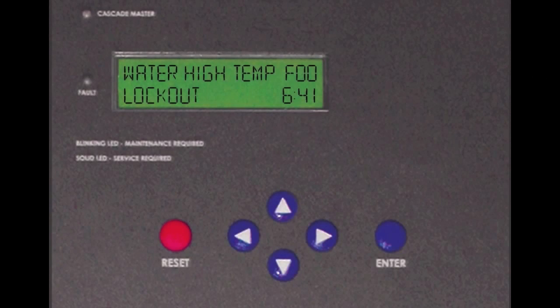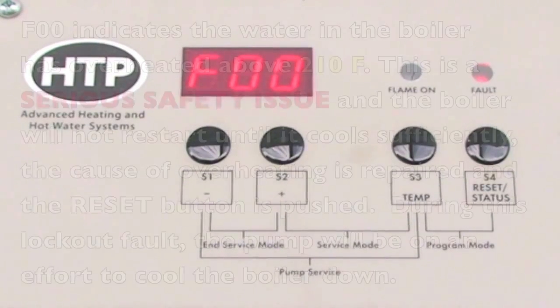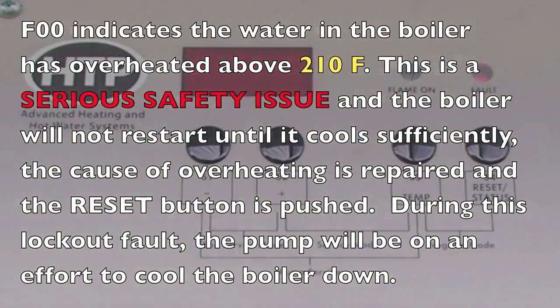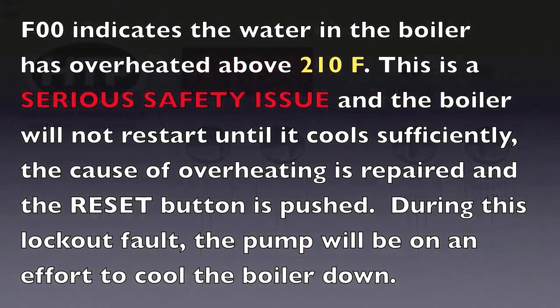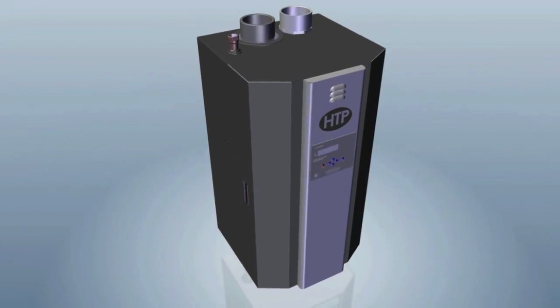If you are getting an F00 fault on your display, this fault occurs when the high limit switch has been exceeded above the boiler's established safety limit temperature of 210 degrees F. Be very cautious, as the heater temperature could be very high and could cause scalding temperatures and injury.